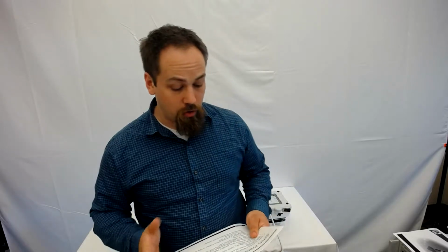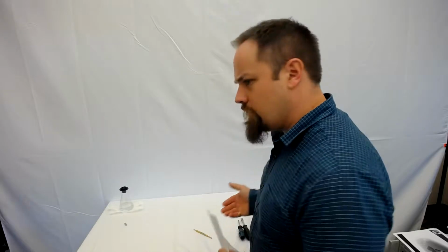Before we start, we should go through a few safety precautions. The main thing here is refer to your full service manual for all the safety precautions. I'm only going to hit a few different bullet points here. The first thing is to only connect to a power supply via the properly rated grounded electrical outlet. So make sure you're not plugging in a 120 unit to a 230 volt source. Make sure that your rating is correct. And particularly on this unit, we are going to be using a power supply that doesn't fluctuate. So we're going to be using a voltage generator, and that's going to be very important for your calibration and getting a good quality calibration.